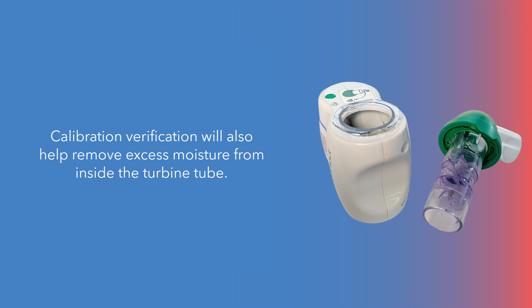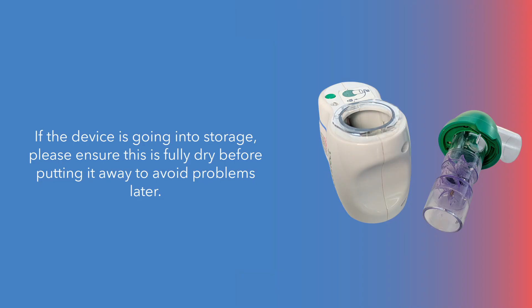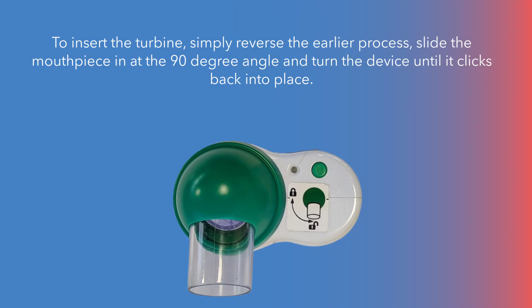Calibration verification will also help remove excess moisture from inside the turbine tube. If the device is going into storage, please ensure this is fully dry before putting it away to avoid problems later. To insert the turbine, simply reverse the earlier process, slide the mouthpiece in at the 90-degree angle and turn the device until it clicks back into place.